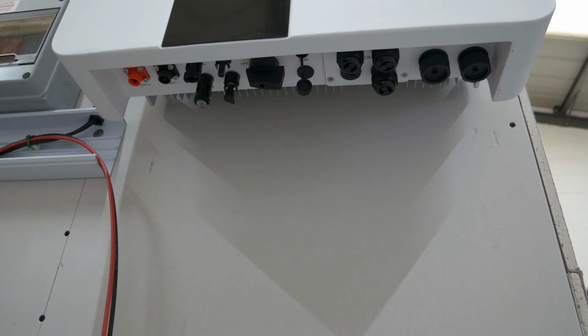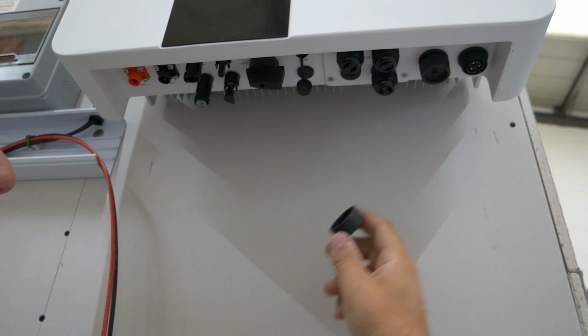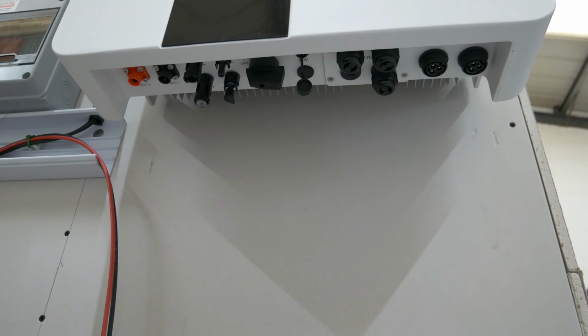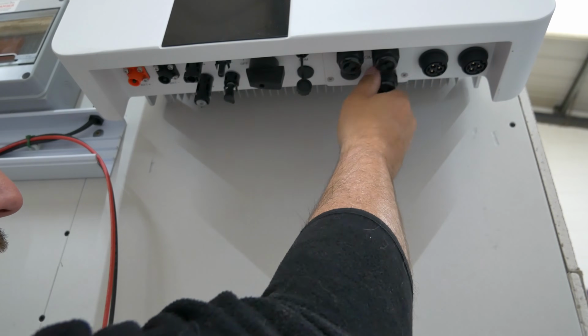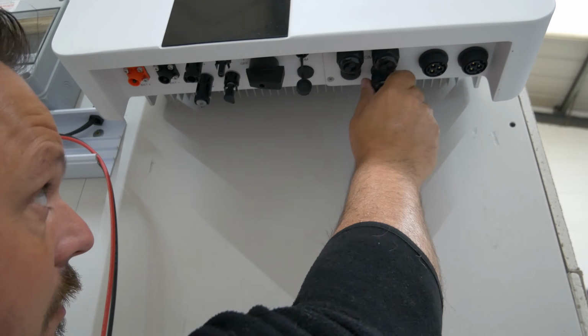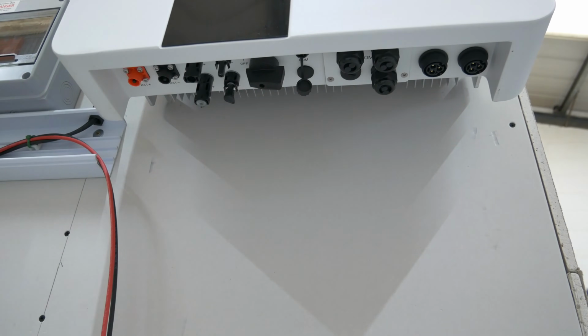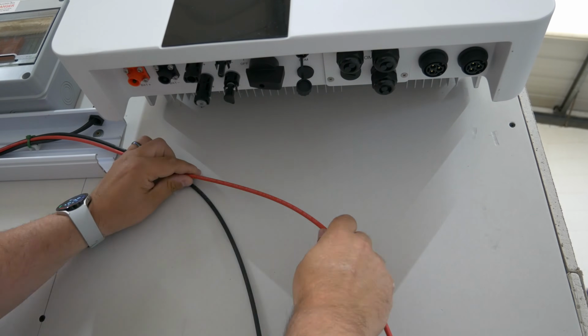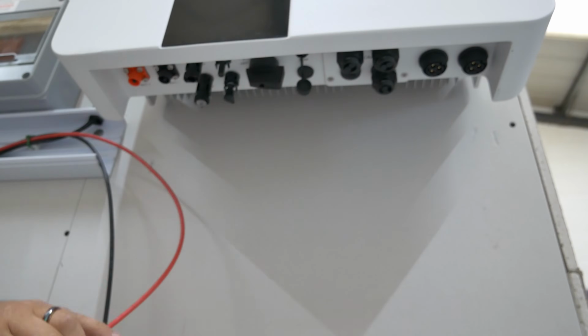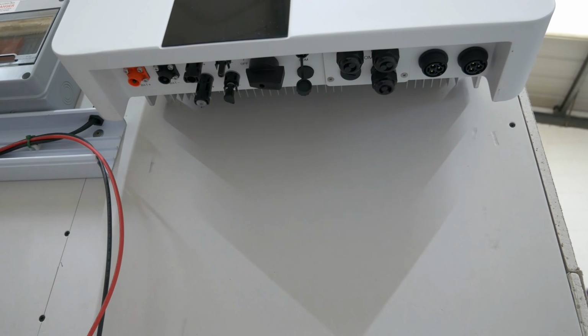On the underside of the inverter you've got your battery inputs, your PV inputs, the DC isolators, the communication ports, access to make your terminations through the cat cables for the CT and BMS, and then the EPS and grid connections. We're going to start with the PV cabling, using the LK kit again.